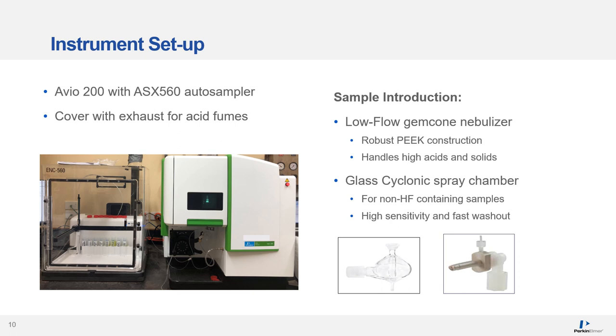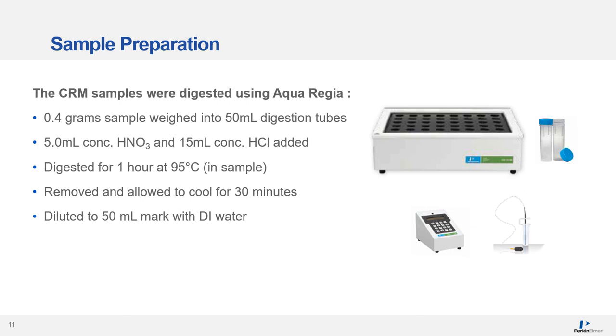The sample introduction consisted of a GemCone nebulizer, which is a robust PEEK construction suited for these types of samples, and a default glass cyclonic spray chamber — with the option of a Scott-type spray chamber if samples contain hydrofluoric acid. Sample preparation involved aqua regia digestion: 0.4 grams of sample was weighed into a digestion tube, nitric and hydrochloric acids were added, the samples were digested for one hour at 95 degrees Celsius, then allowed to cool and diluted to the 50 mL mark with deionised water.